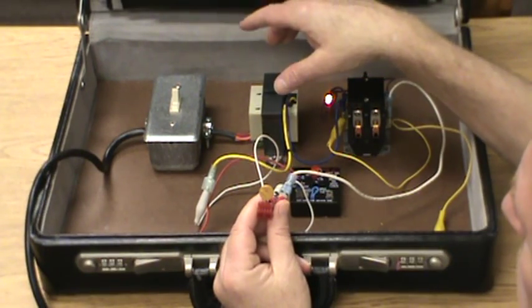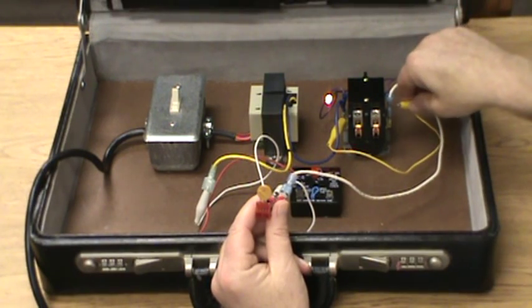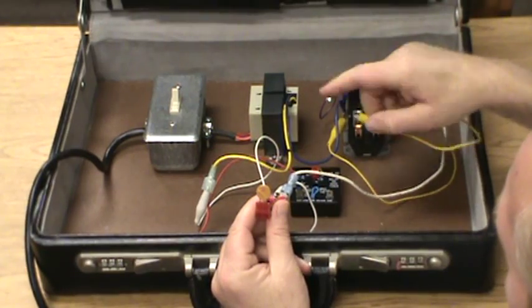When this trips, of course it protects all the circuits of the furnace and also this transformer. I'll trip it again - I put the short across this coil and you can see the little LED light went out.